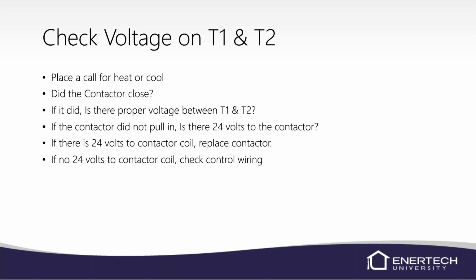If the contactor did not pull in, obviously check for 24 volts from the contactor or to the contactor. If there is 24 volts to the contactor, then obviously the coil in the contactor is bad and you'll need to replace the contactor. If there's no 24 volts, you'll want to trace it back. It goes back to the lockout board. Make sure that your safeties are all closed. It's very possible that a light could burn out on the board and it's showing and it's really in high pressure or something like that. So always double check to make sure that the high pressure, low pressure switches are closed. If you've got a flow switch, you could jumper that out and make sure that circuit's good as well.